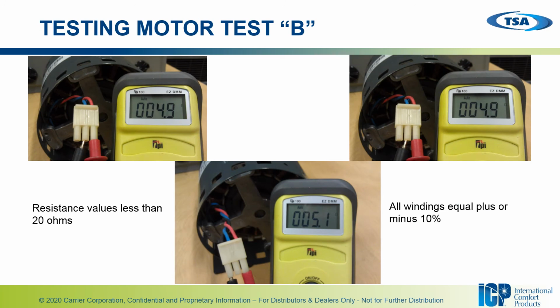Okay, and motor test B, this is going to be the winding to winding resistance. You should be typically less than 20 ohms. It is a three-phase motor, so all of your windings should be pretty close to equal, plus or minus 10%, which is the typical rule of thumb in electrical.